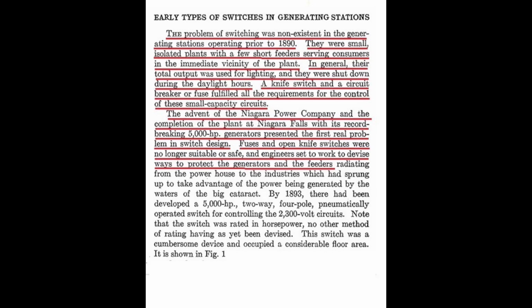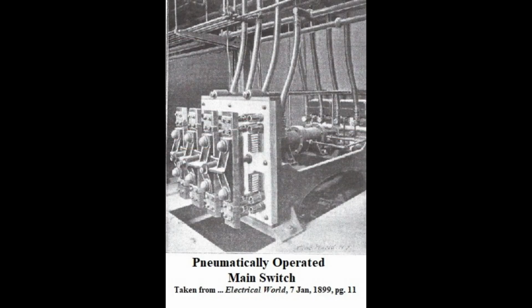Fuses and open knife switches were no longer suitable or safe, and engineers set to work to devise ways to protect the generators and feeders. One outcome of this was the 5,000 horsepower 4-pole switch shown here. The 4 poles were required for the two-phase system in use in this plant. The poles were operated by compressed air and placed in an enclosed gallery so that no operator would be exposed to the arc drawn when the switches were open under load.